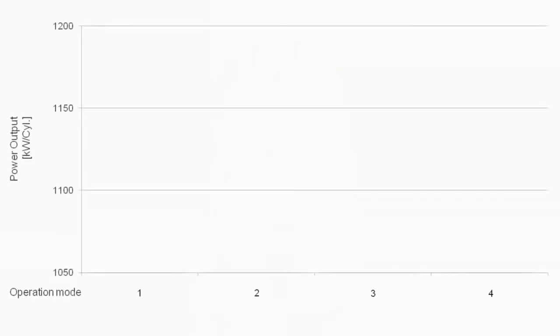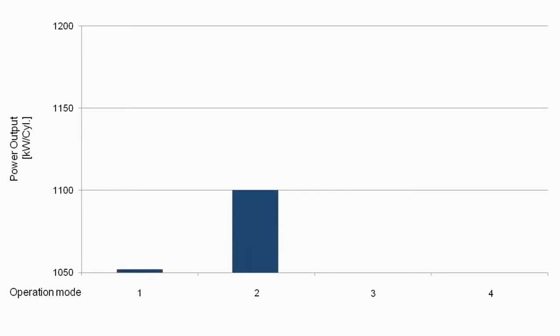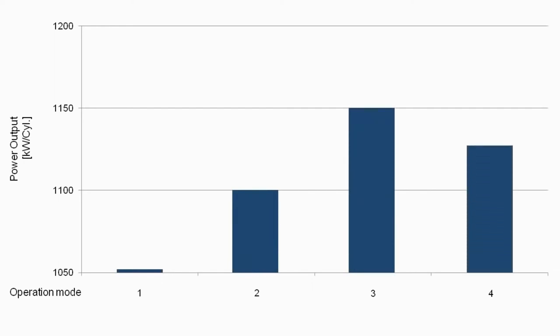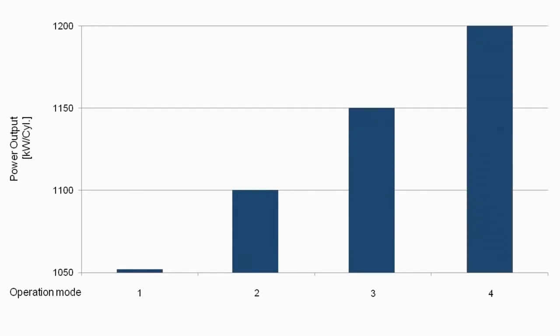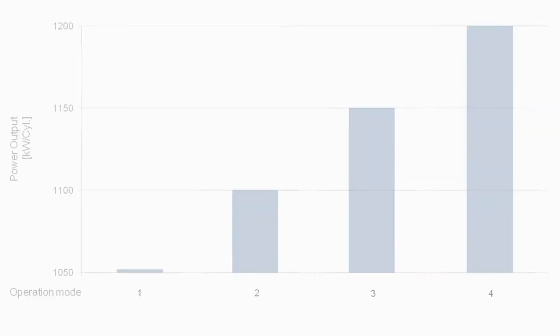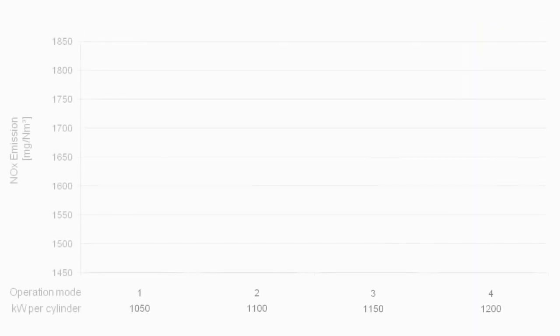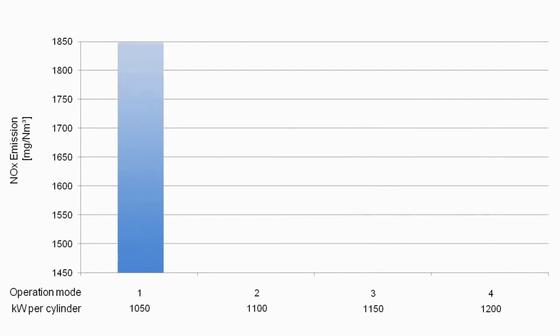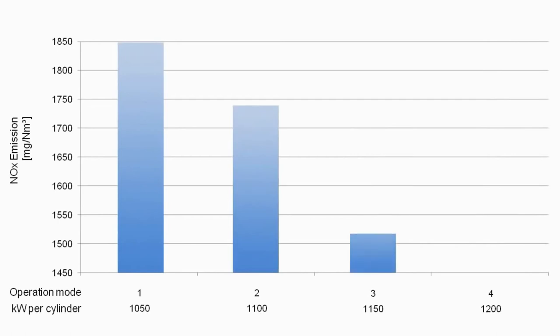The benefits of the two-stage turbocharged 18V48/60TS speak for themselves. Depending on operation mode, the continuous power output of the engine can be increased from 1,050 to 1,200 kilowatts per cylinder. The nitrogen oxide emissions can be reduced from the level of 1,850 milligrams per standard cubic meter, stipulated by the effective World Bank guideline, down to 1,480 milligrams per standard cubic meter.